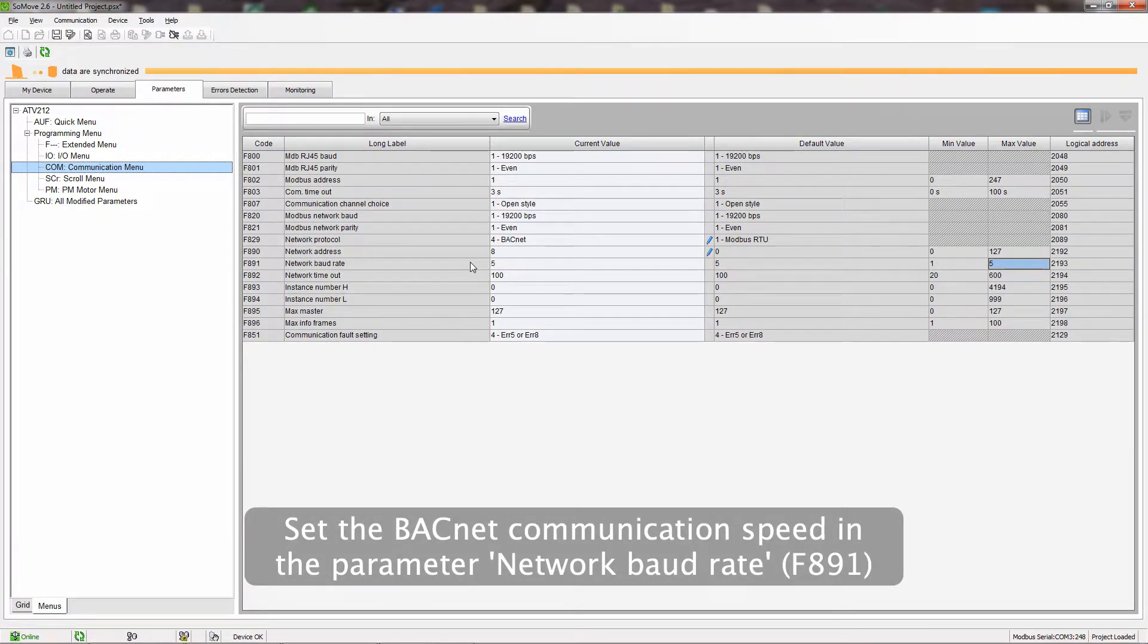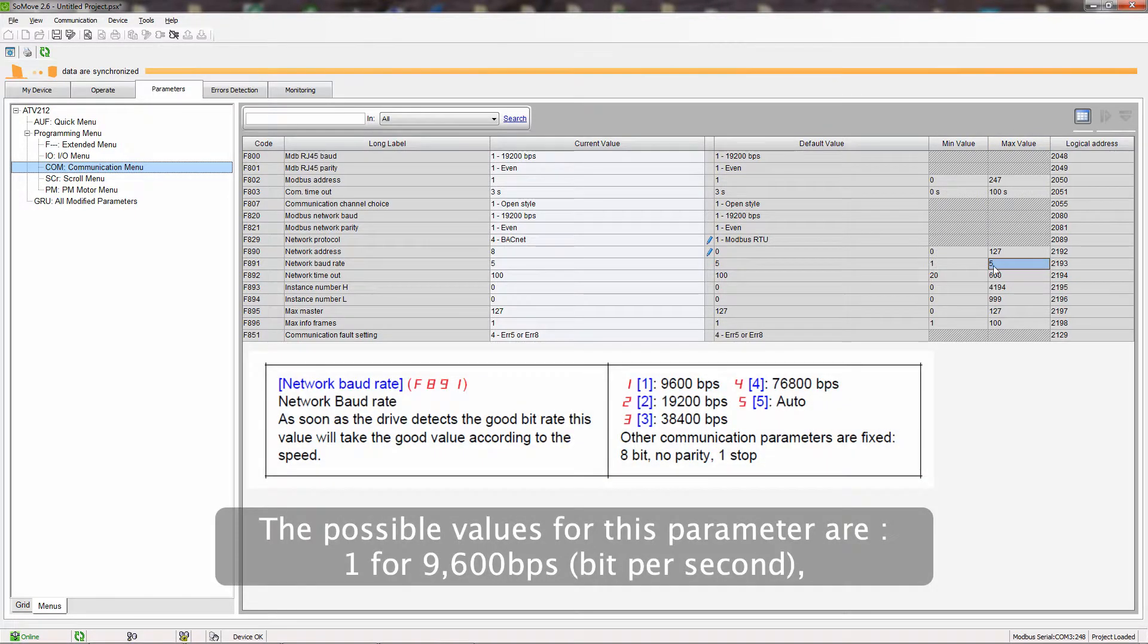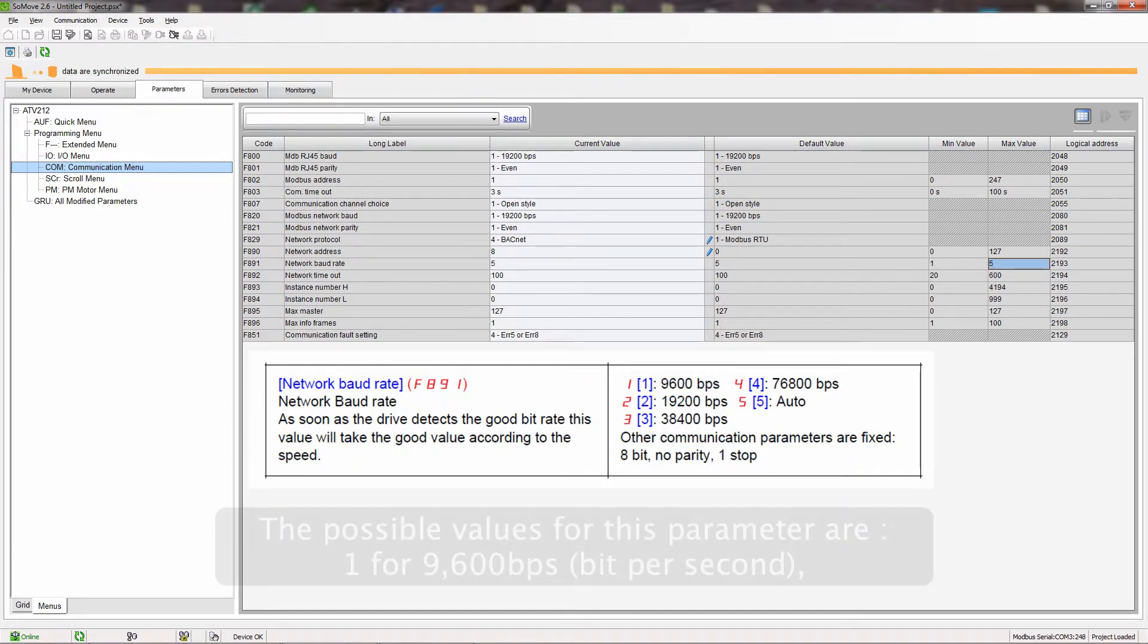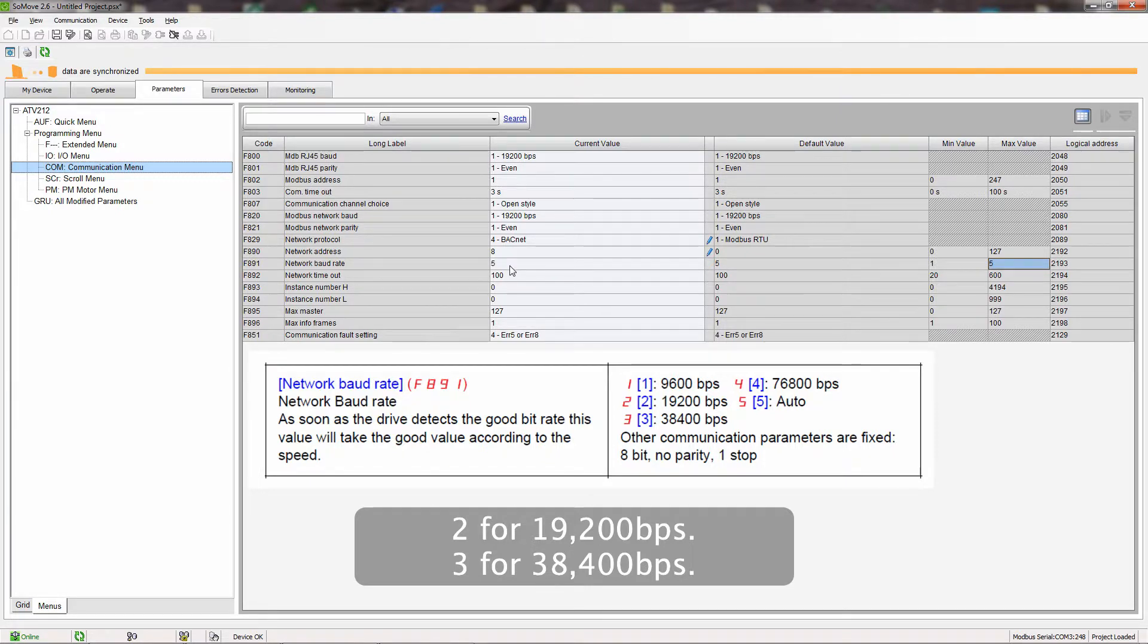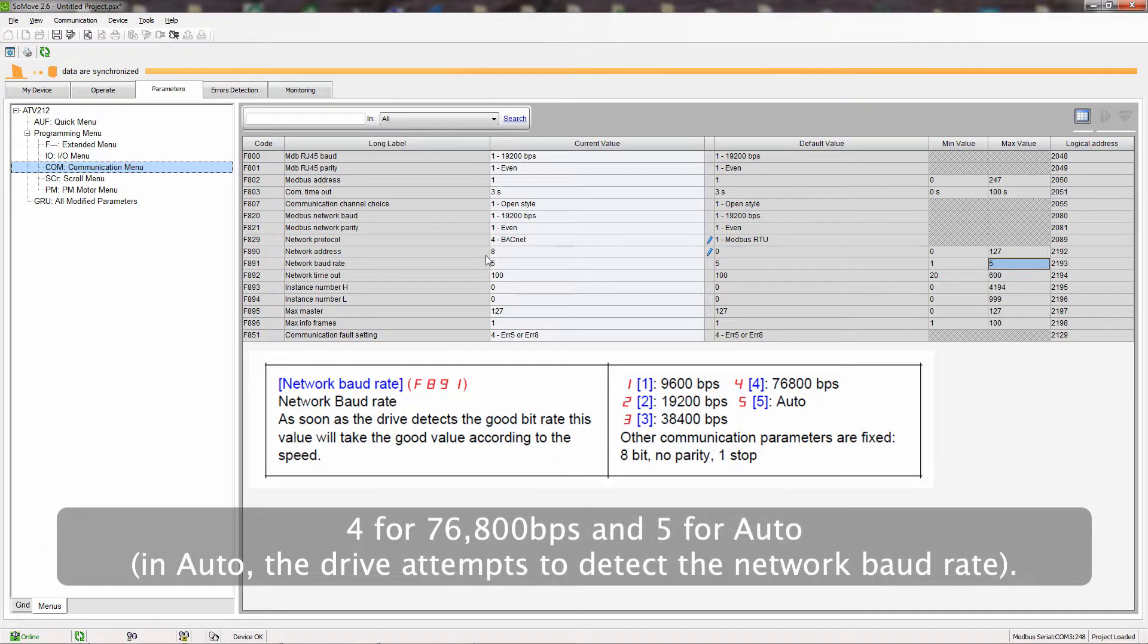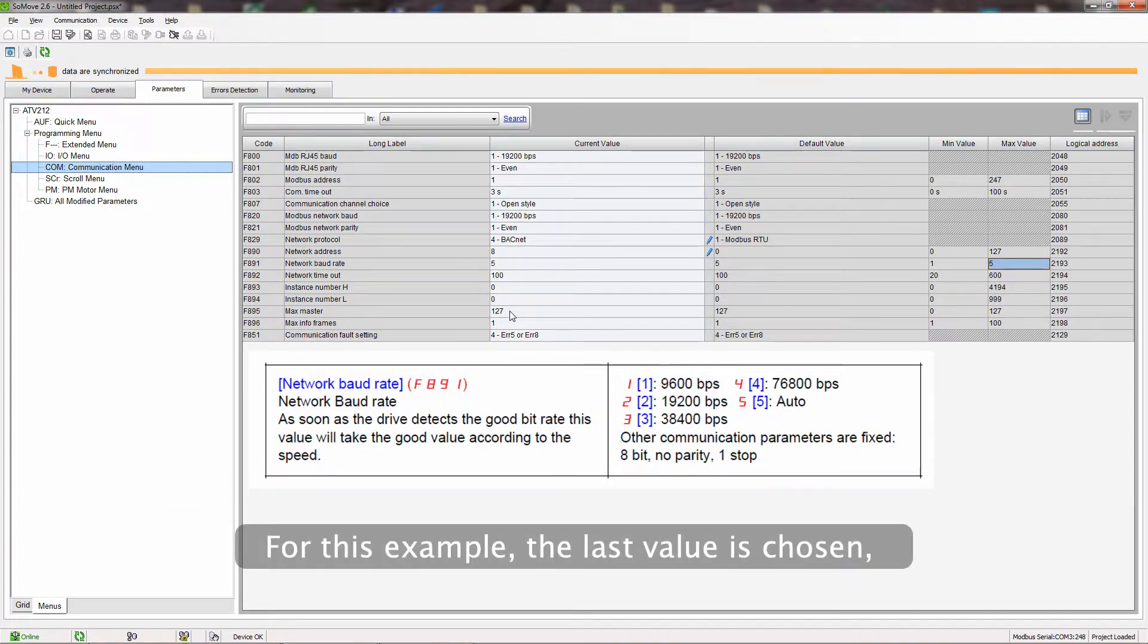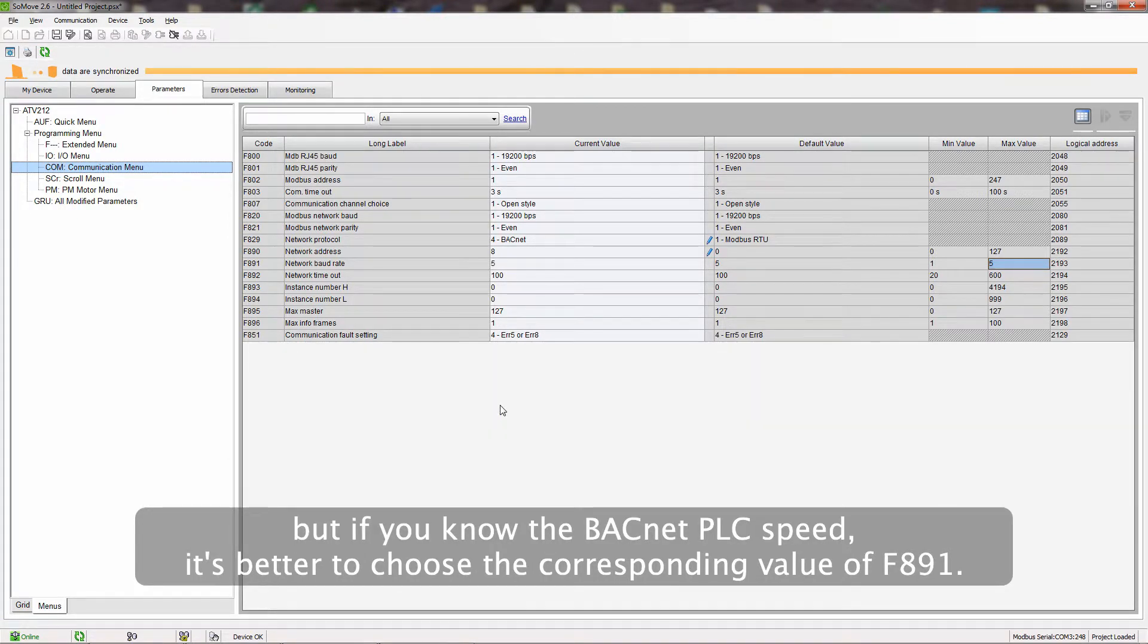Set the BACnet communication speed in the parameter Network Baud Rate. The possible values for this parameter are 1 for 9600 bits per second, 2 for 19,200 bits per second, 3 for 38,400 bits per second, 4 for 76,800 bits per second, and 5 for Auto. In Auto, the drive attempts to detect the network Baud Rate. For this example, the last value is chosen, but if you know the BACnet PLC speed, it's better to choose the corresponding value of F891.